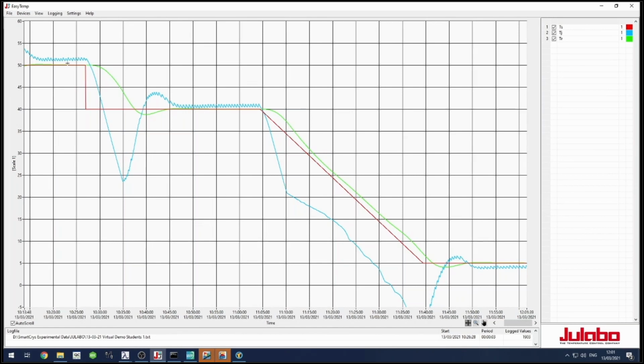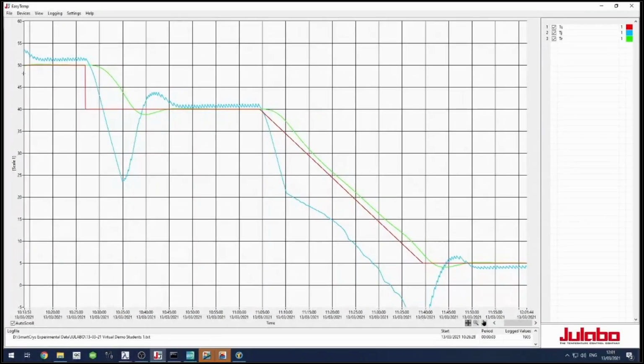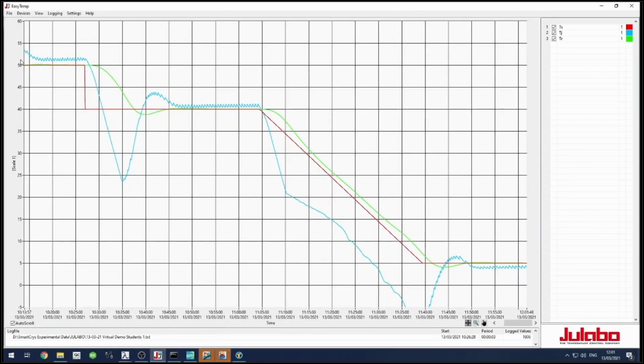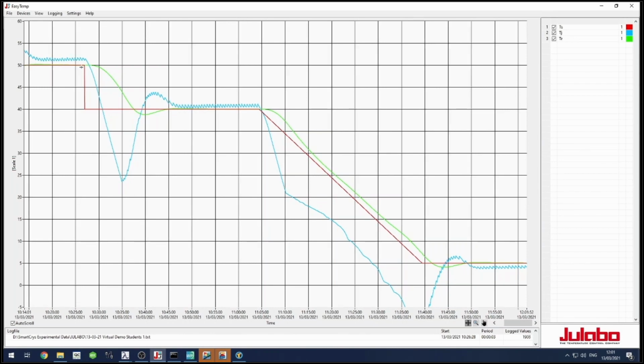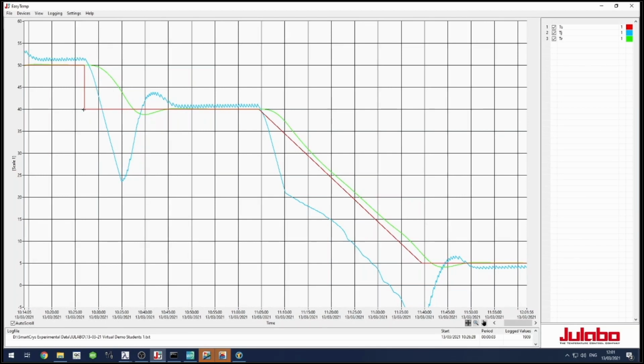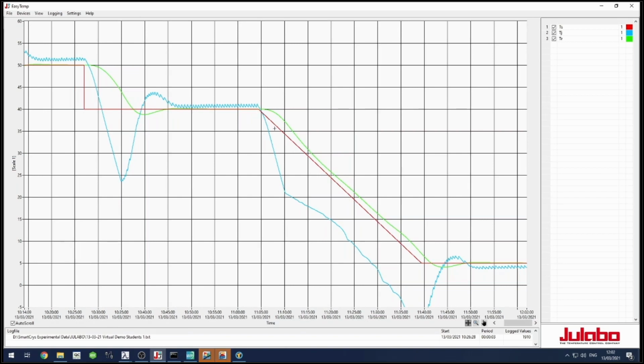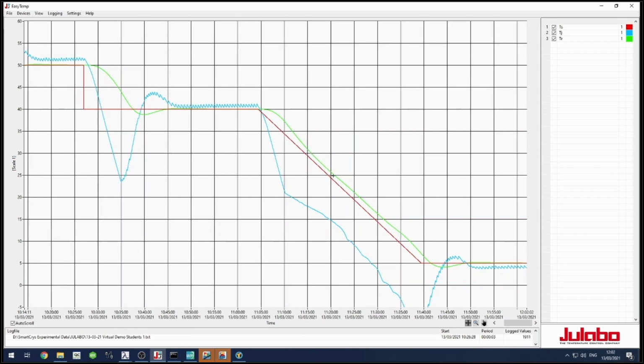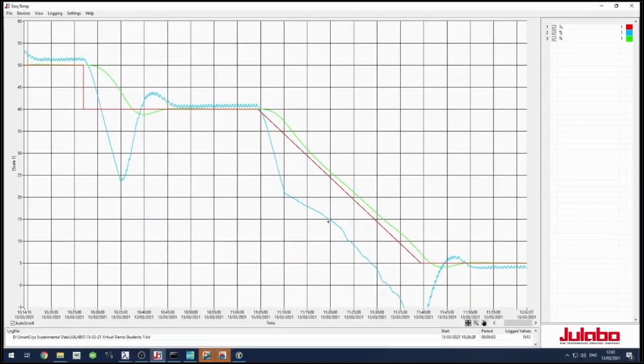Sorry, I believe there was a problem with the audio, which I made worse. Okay, so what we're looking at here in red was the set point. Initially, the temperature of the chiller was set at 50 degrees. In the recipe, the next step was to go to 40 degrees, and then to slowly allow the temperature of the reaction to drop down to 5 degrees. Those were the steps in the process, and the steps in the recipe.